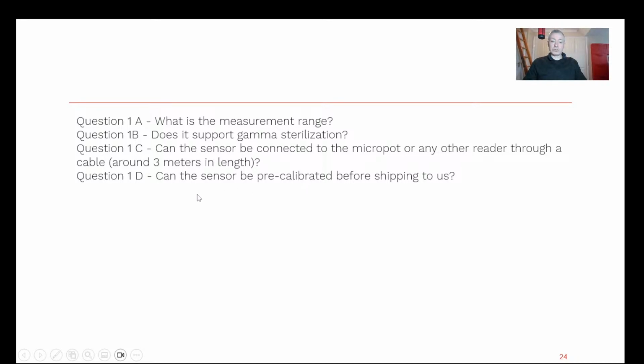We do support gamma radiation. We have sterilization projects running at the moment where we test sensors, send them through the client's product and sterilization process, and then test the sensors again. When doing sterilization, if I put a sensor here and the sterilization source is there, I'm essentially in the shadow of the device. I know these things rotate within the chambers, but you have to think about the sensor in the application, and about how the radiation is directed onto the device. If you're behind a certain blocking material, that would cast a shadow. So you can't just make a blanket statement, you have to do the work. Three meters, I think, is quite low risk, but we'd have to do a mini project to test it.